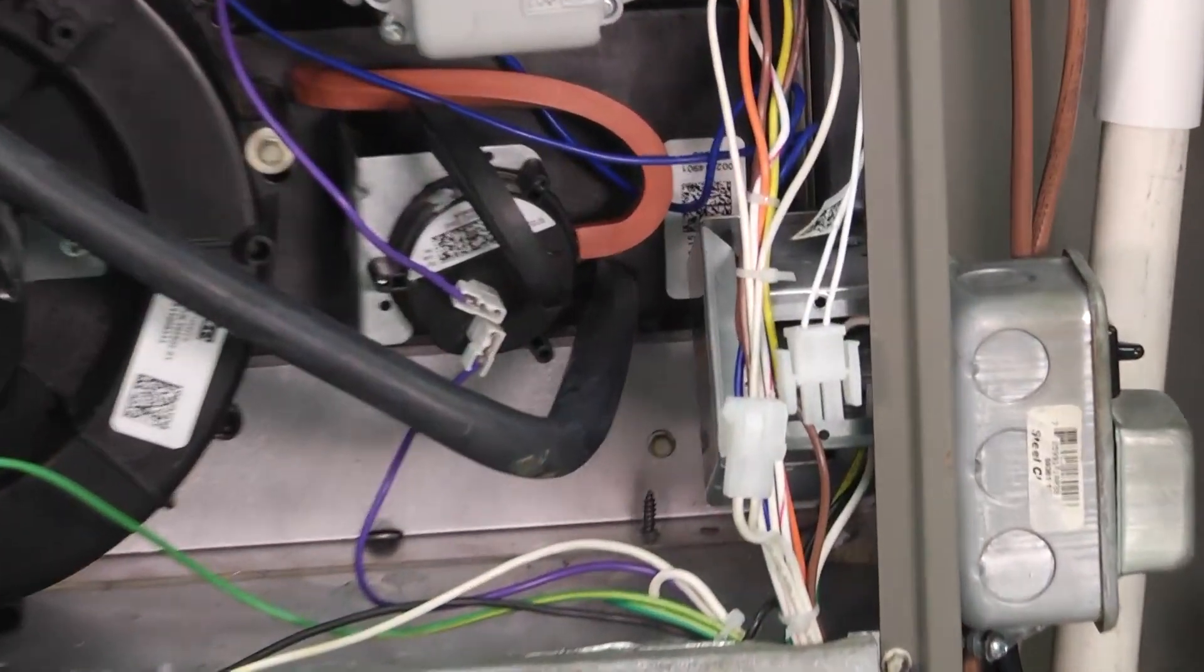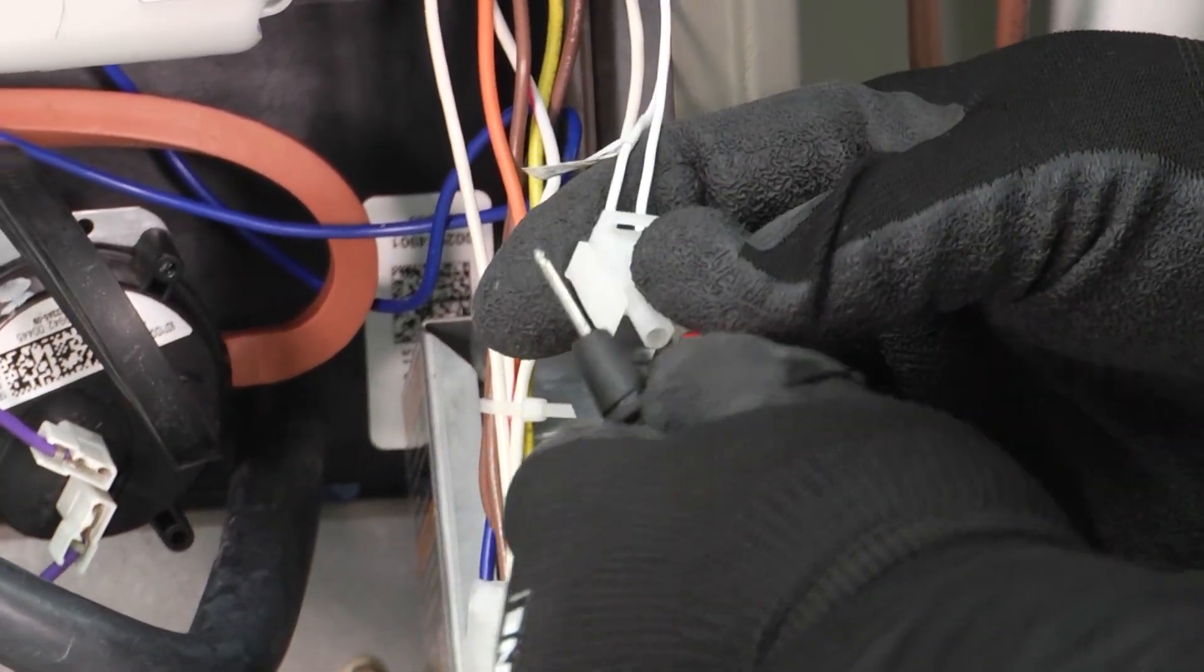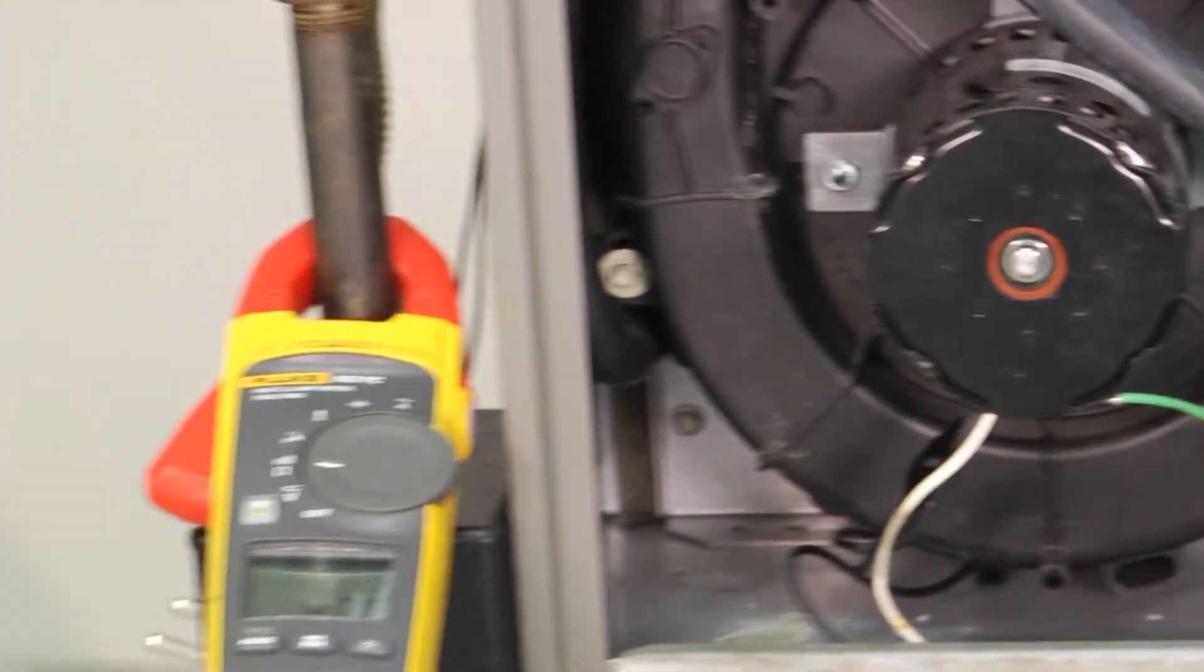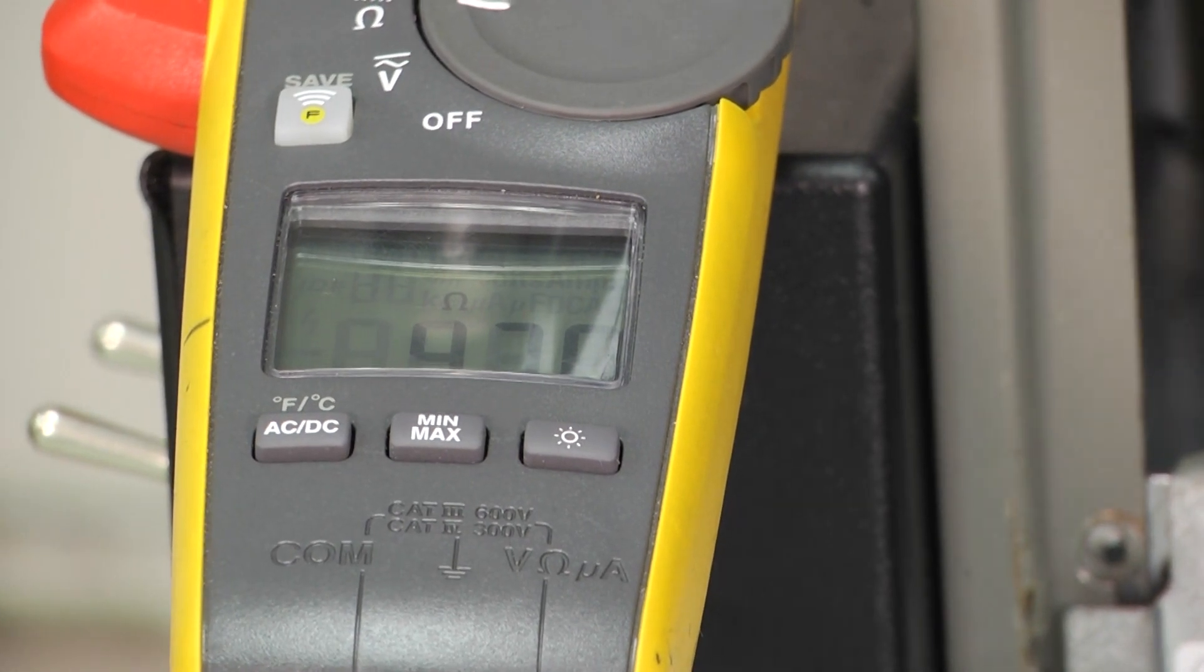Then all we simply do is we unplug our hot surface igniter here. I'm going to switch sides and we'll be able to go look at our meter over there. And I'm going to insert my leads into the holes there and then I'm going to get an ohm reading. And this one is reading at 47, 47 ohms.